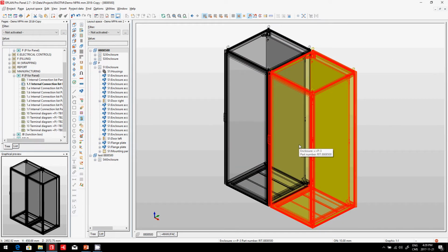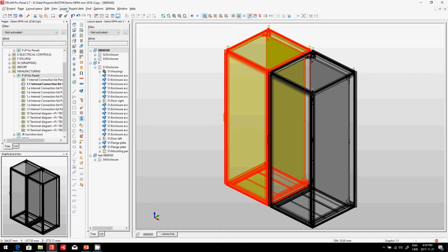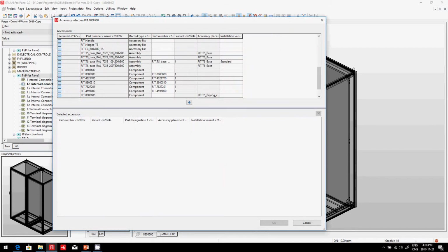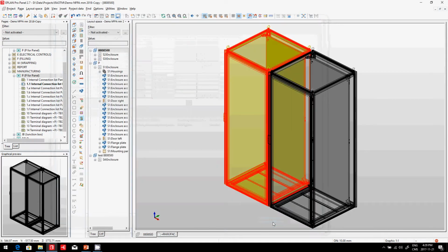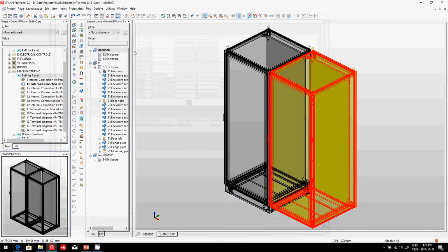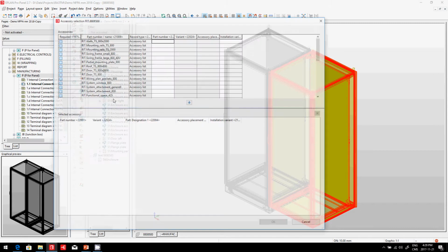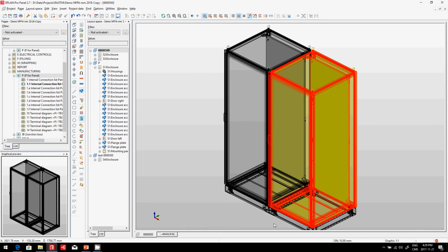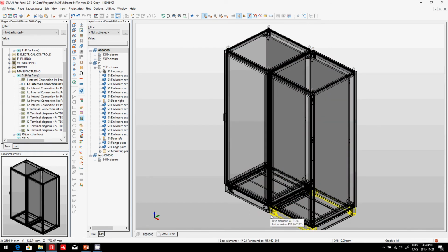So one typical accessory that some people may actually add, and you can see this here with the insert accessories. When you pick this, you can see that there are a whole bunch of accessories that are possible. I'm actually going to go here with the cable base. This is a small cable base that can be added, and you just specify here, boom, that you want it. You can do it on the second panel, of course, also. In this particular case it's 100 millimeter, roughly a 3-inch base, in which your cables can come in, and it is automatically placed down at the bottom there.